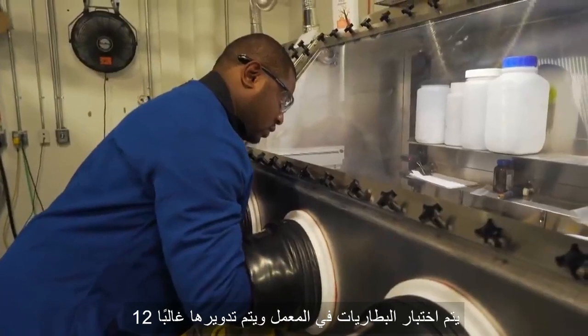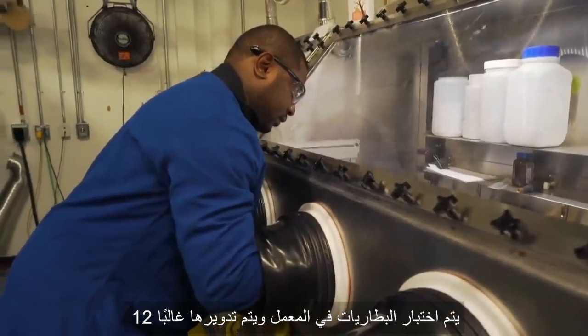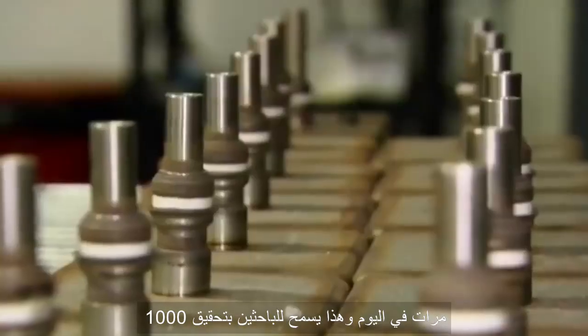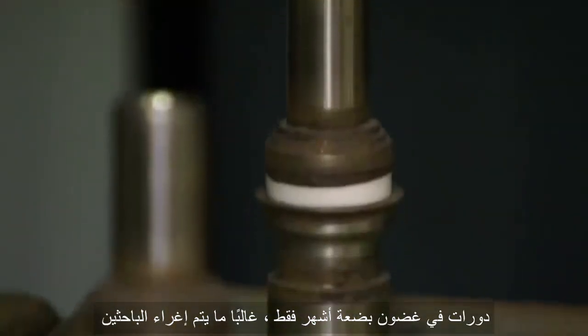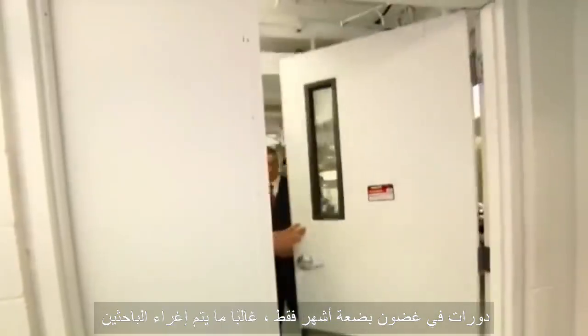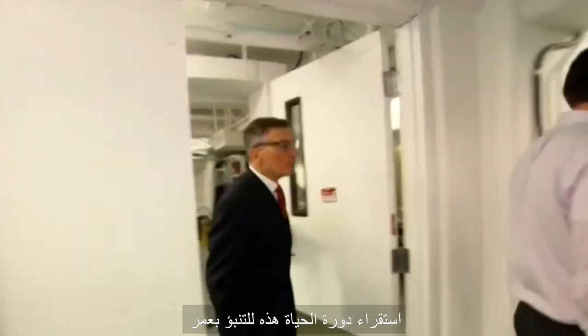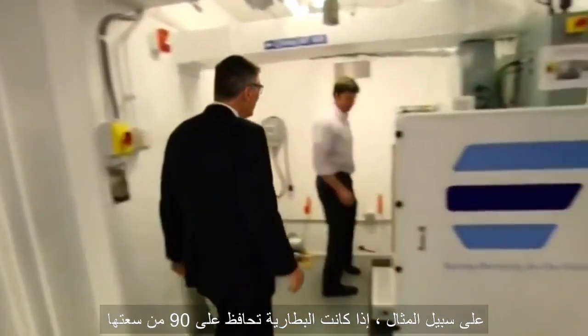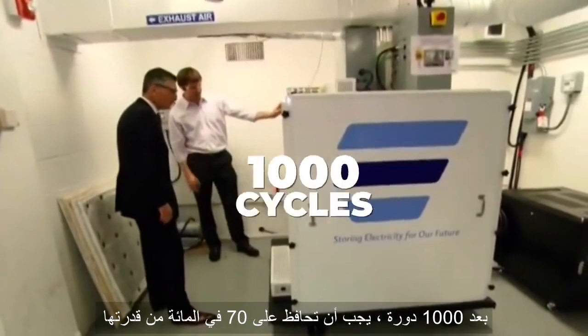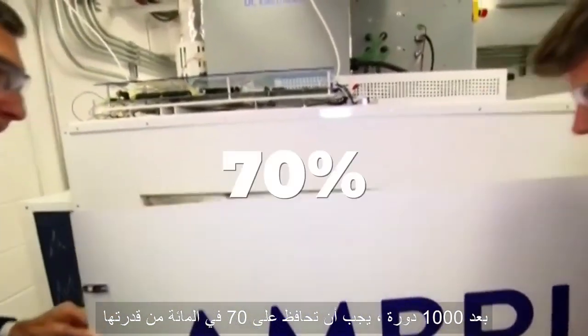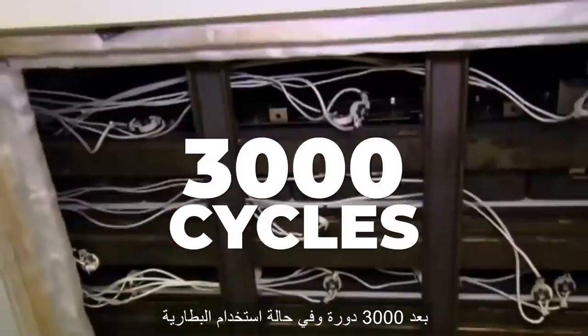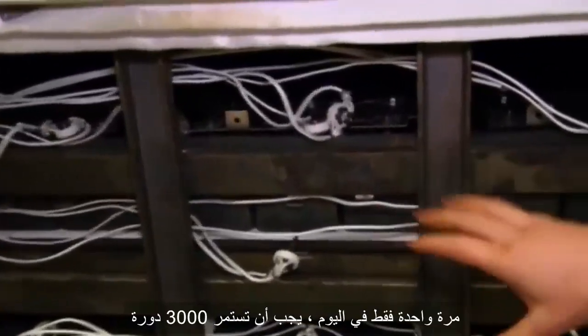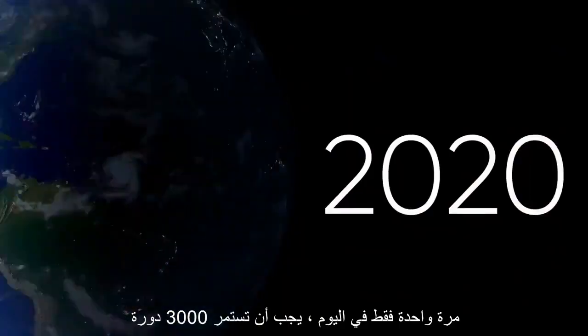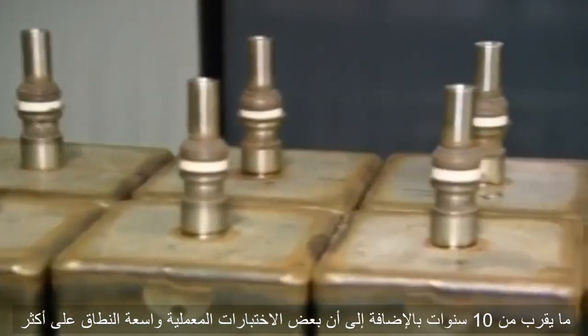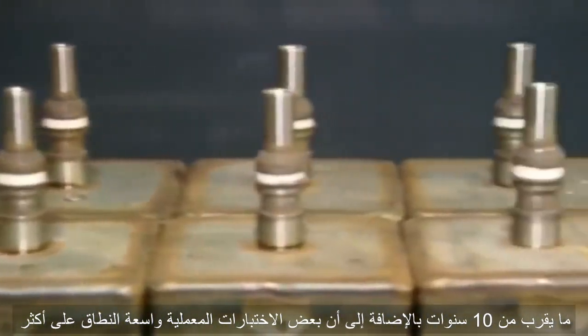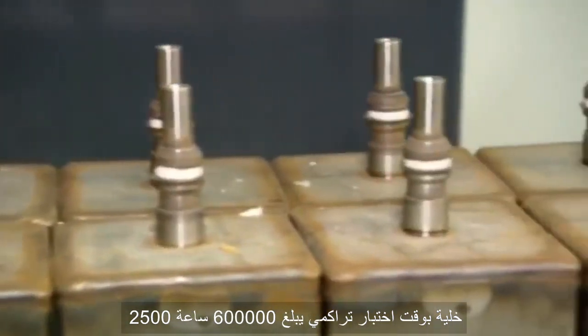They claim that when batteries are tested in the lab, they are often cycled 12 times per day. This allows researchers to achieve 1,000 cycles in just a few months. Researchers are often tempted to extrapolate this cycle life to predict a lifespan. For example, if a battery maintains 90% of its capacity after 1,000 cycles, then it should maintain 70% of its capacity after 3,000 cycles. And if the battery is used just once per day, then 3,000 cycles should last nearly 10 years.